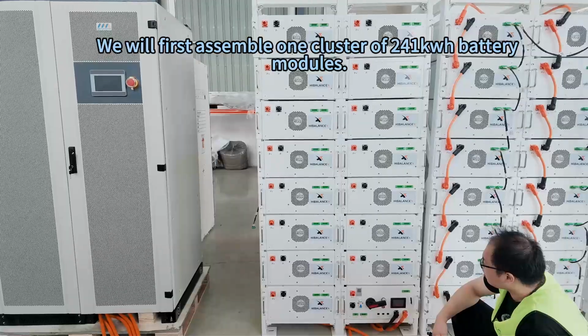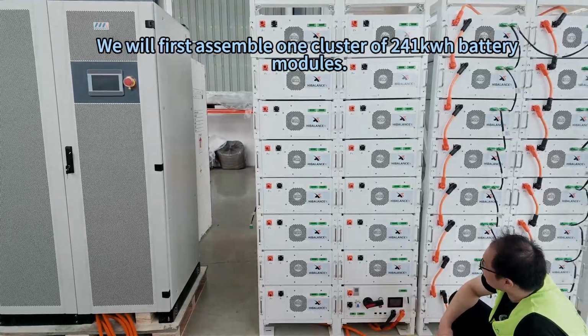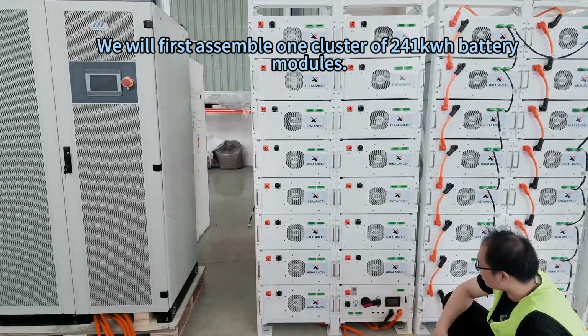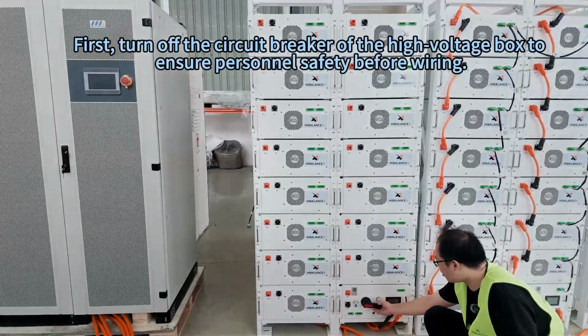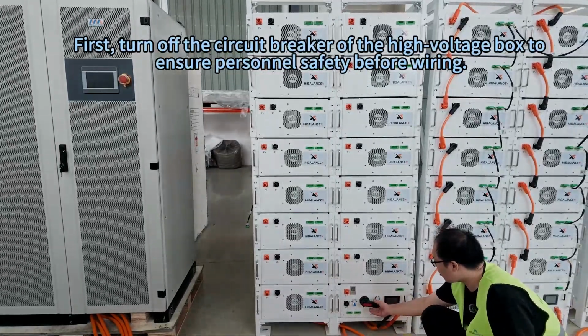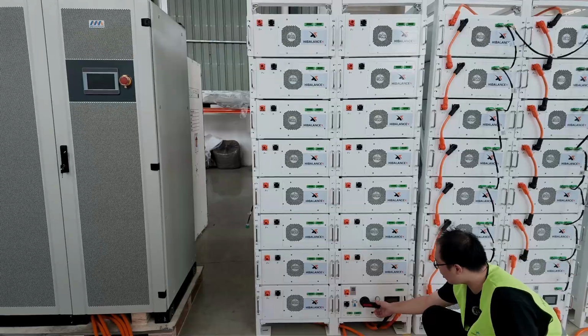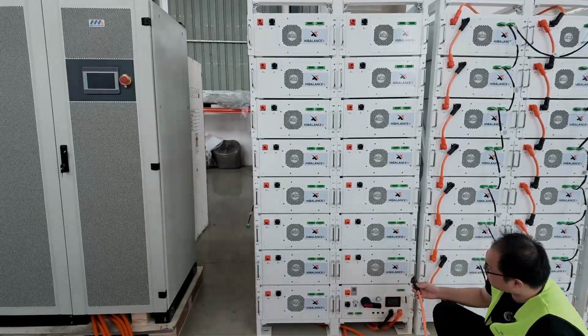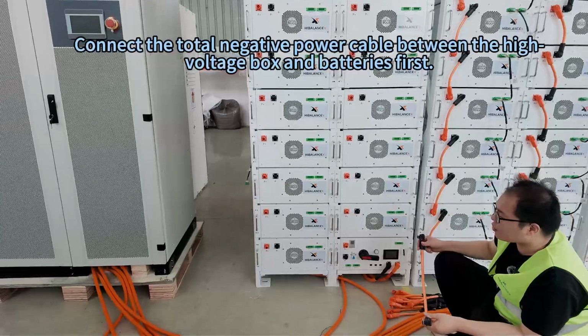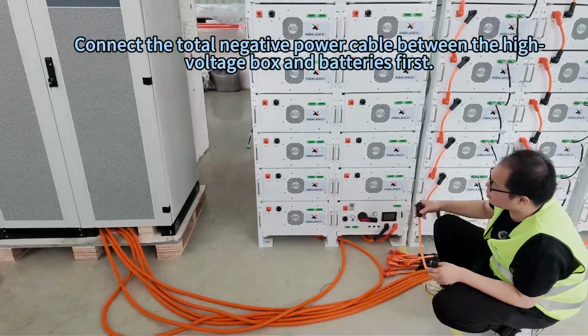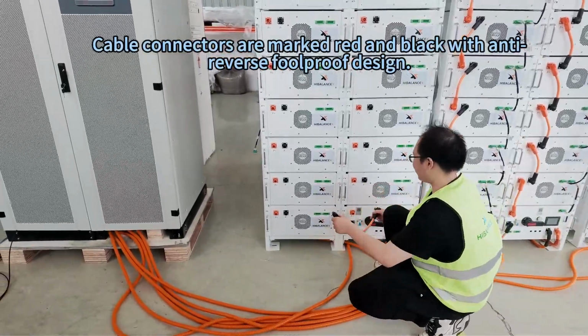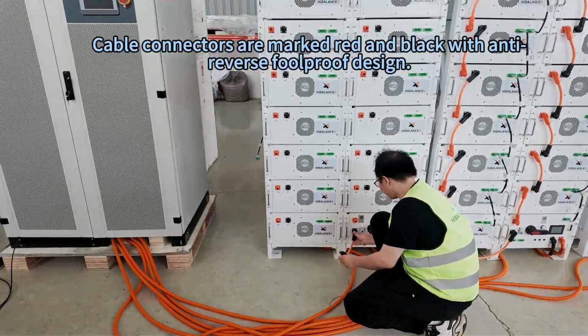We will first assemble one cluster of 241 kilowatt-hour battery modules. First, turn off the circuit breaker of the high-voltage box to ensure personnel safety before wiring. Connect the total negative power cable between the high-voltage box and batteries first. Cable connectors are marked red and black with anti-reverse foolproof design.